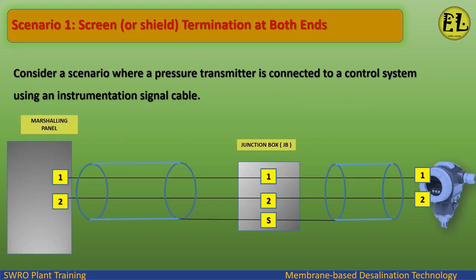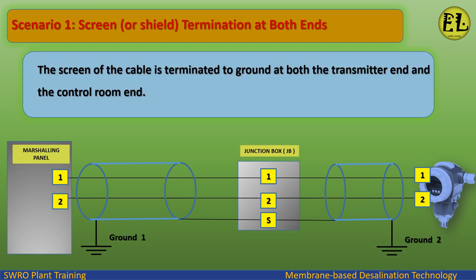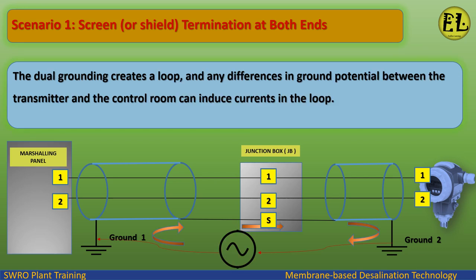Scenario 1: Screen or shield termination at both ends. Consider a scenario where a pressure transmitter is connected to a control system using an instrumentation signal cable. The screen of the cable is terminated to ground at both the transmitter end and the control room end. This dual grounding creates a loop, and any differences in ground potential between the transmitter and the control room can induce currents in the loop.